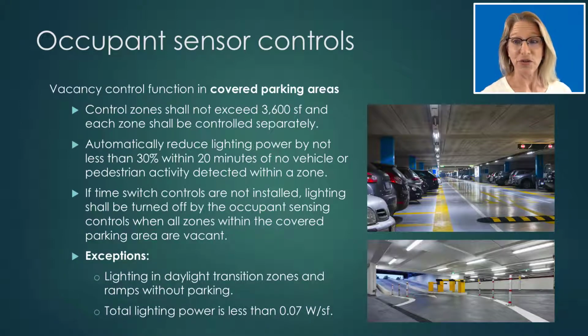Light reduction controls are not required for lighting within the entry ramp. This is also referred to as the daylight transition zone. Lighting is needed within this area to help the driver's eyes adjust to the abrupt change in brightness from the outdoors to the parking garage. Occupancy sensor controls are also not needed in parking garages served by very low wattage lighting, defined as less than 0.07 watts per square foot.